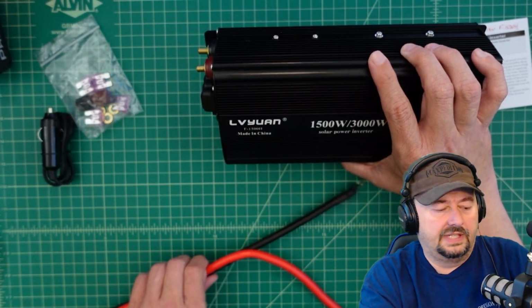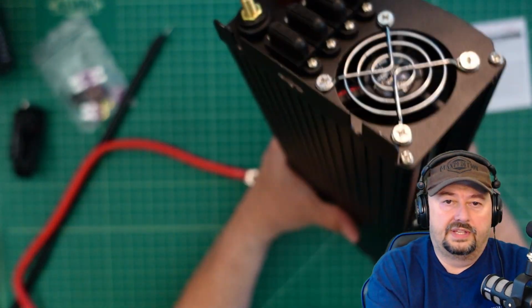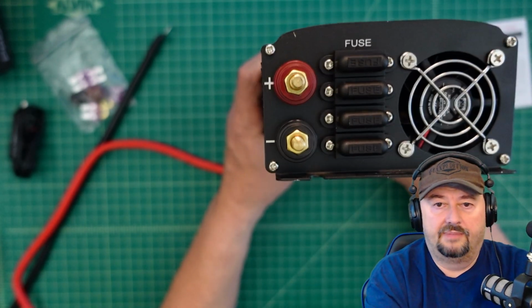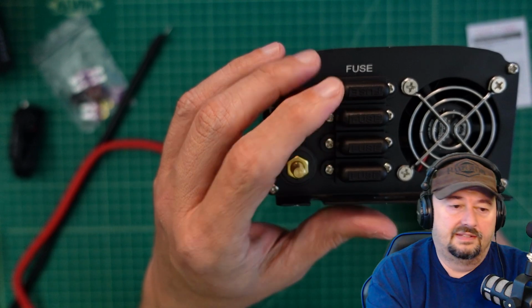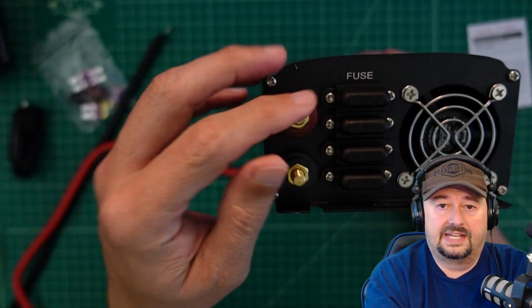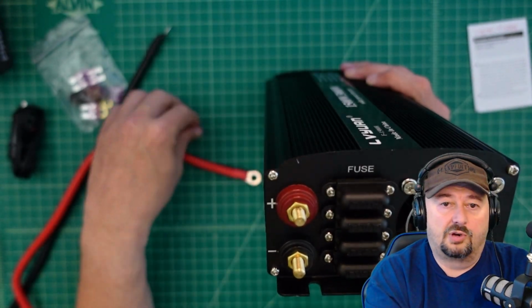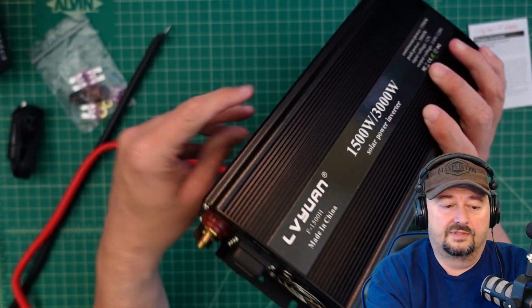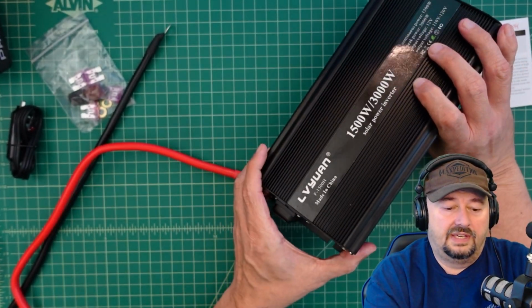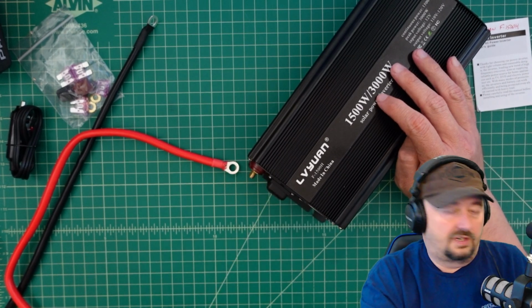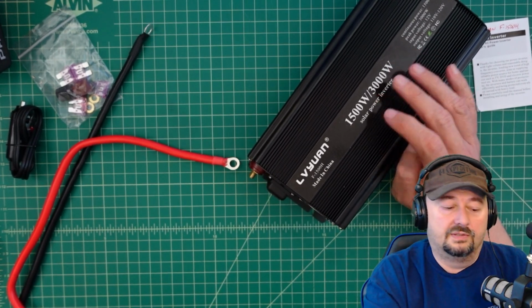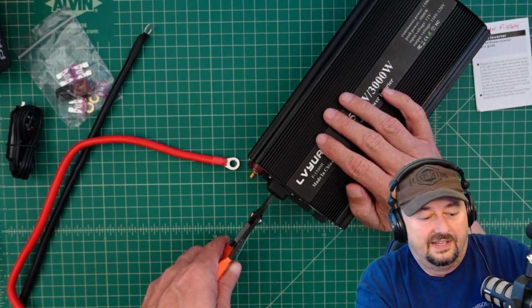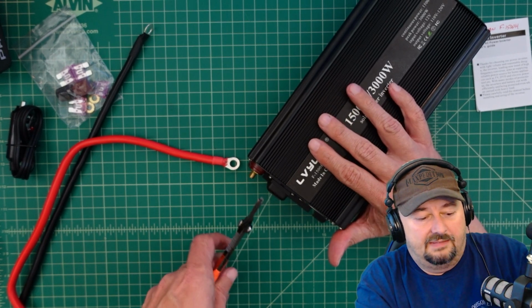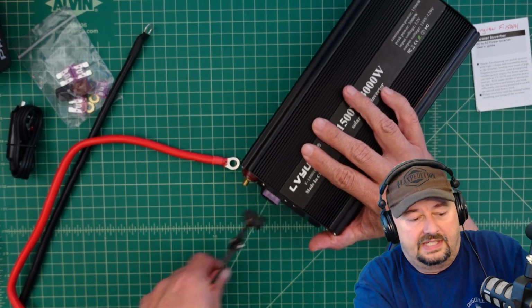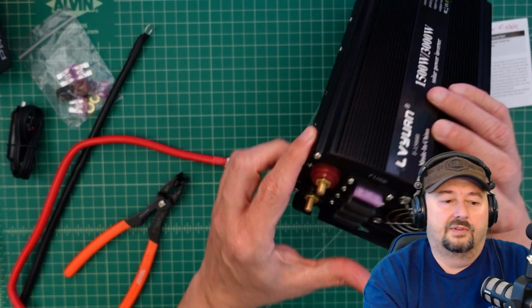Now, taking a look at the inverter, one of the things I wanted to point out on the back is that it gives you access to the fuse panel, which is fantastic, because a lot of times you have to take these inverters apart to get to the fuses, and they're very difficult to reach. In some cases the fuses are actually soldered to the system board, making replacement very difficult. Here, it's just an easy job to go ahead and replace them.